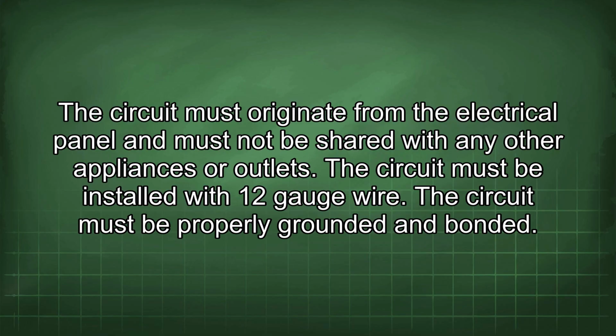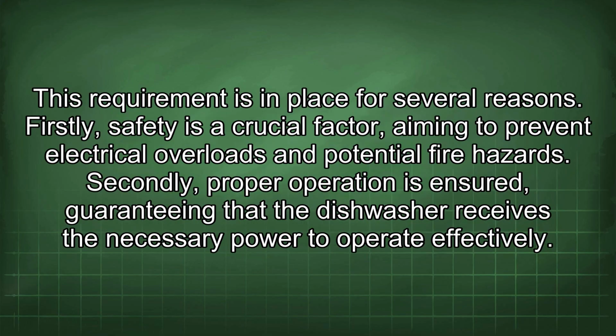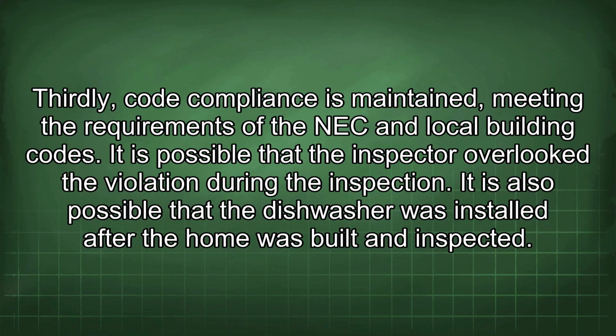The circuit must be installed with 12-gauge wire. The circuit must be properly grounded and bonded. This requirement is in place for several reasons. Firstly, safety is a crucial factor, aiming to prevent electrical overloads and potential fire hazards. Secondly, proper operation is ensured, guaranteeing that the dishwasher receives the necessary power to operate effectively. Thirdly, code compliance is maintained, meeting the requirements of the NEC and local building codes.